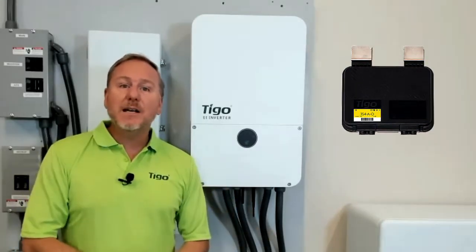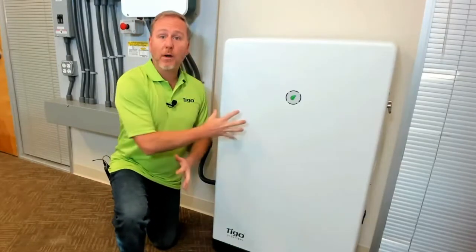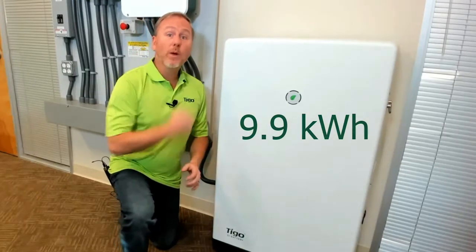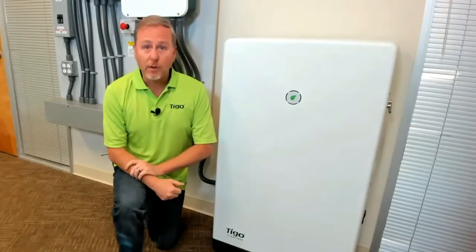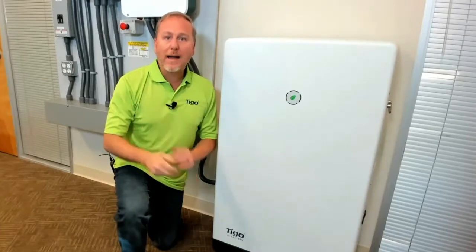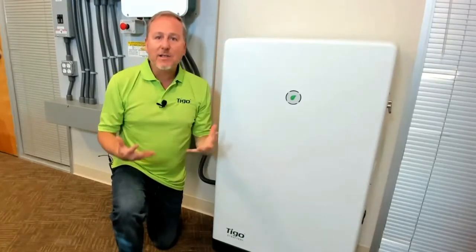Including the Tigo TS4 optimizers, which I'll talk about later. The EI battery cabinet houses three 3.3 kilowatt hour battery modules, making the entire output of a single battery cabinet 9.9 kilowatt hours. This is expandable with two cabinets for a total of 19.8 kilowatt hours, and it's extremely fast and very easy to install. Connecting the EI battery to the EI hybrid inverter takes only three wires: a communication wire and the battery wires, positive and negative. I'll get more into that later, but it's super easy to install.